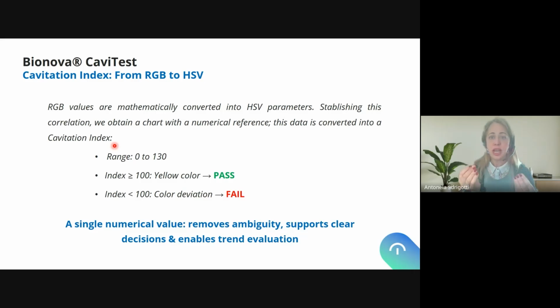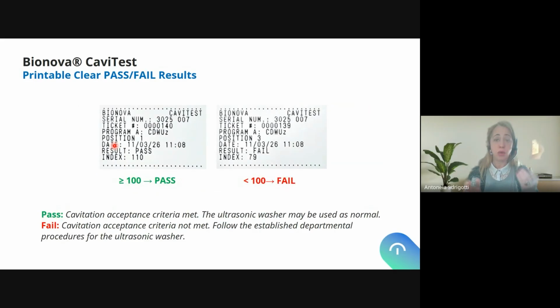Okay, so we translate these very difficult to interpret shades of light green or precise yellow. We translate it thanks to a precise calibrated device and an algorithm that will transform this color interpretation into a precise cavitation index. Okay, so with a single numerical value, we remove the ambiguity, we support clear decisions, and we enable trend evaluation. This is how the ticket will display the results. So you can see that we have clear pass and fail results.